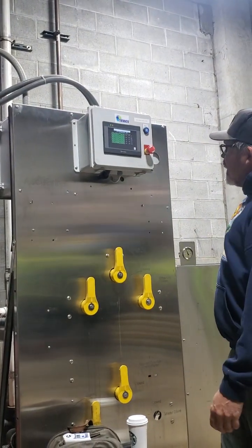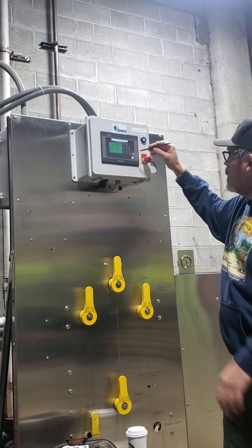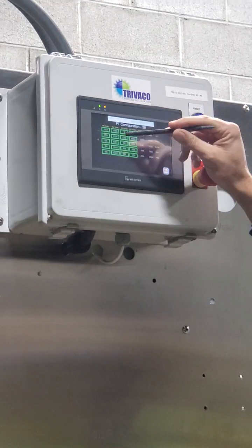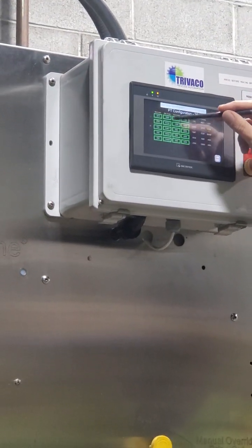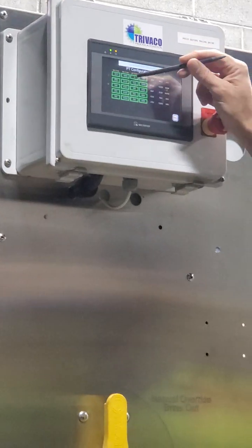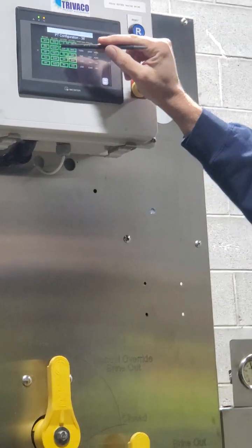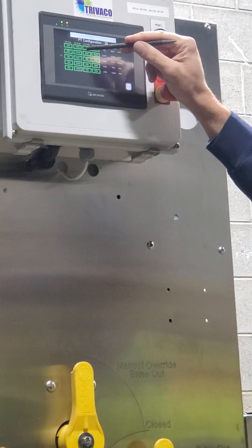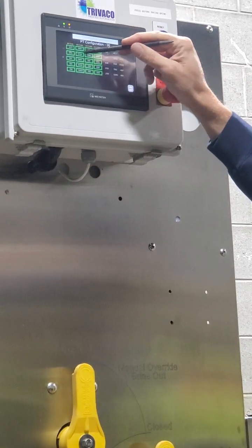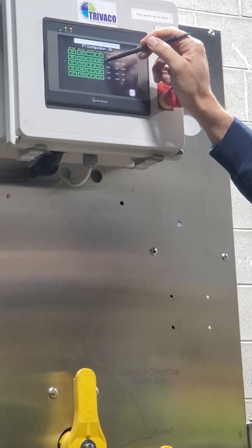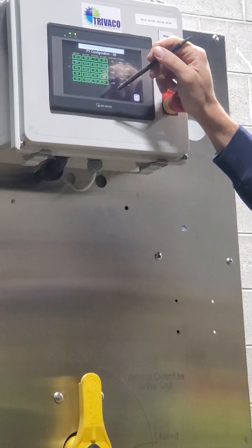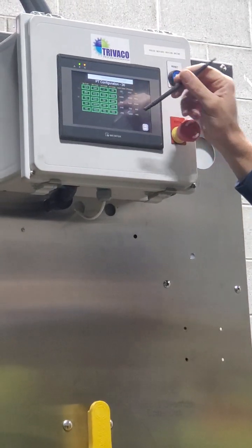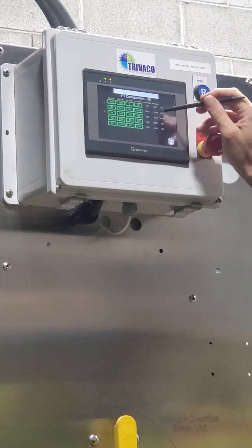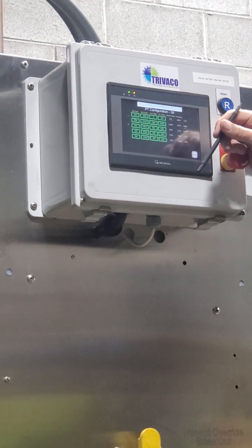So this is the PT reading. Whenever you get your tanks filled up, come in here and check that number. Let's say you get your brine tanks filled all the way up. Right now, when they're entirely filled up, this PT reading should be close to 13,120, and when that number is reached, you have 18,000 gallons in there. So if you ever get your tanks filled all the way up, come in here and double check that number and see how it looks.